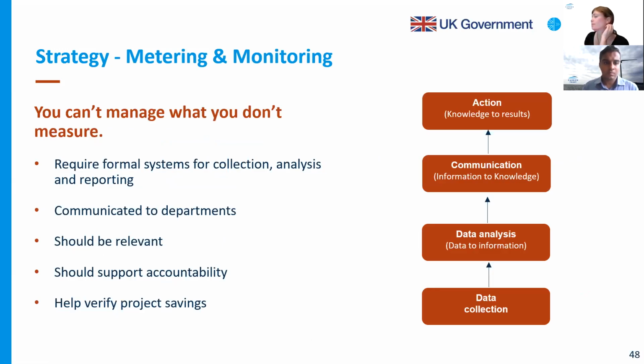Now, effective energy management requires formal systems to be in place for data collection and analysis. So metering and monitoring systems are there to give the energy manager that timely and relevant information on energy use. They're there to provide the ability to investigate energy performance further and take action to rectify performance issues. They're also able to provide energy reports to support accountability for energy use and that ability to verify energy savings following the implementation of new projects. And the senior management team should also receive regular reports that are generated by the system in order to assess the progress with implementing the energy strategy and seeing whether what's happening is meeting policy objectives that they had signed off on. Next slide.